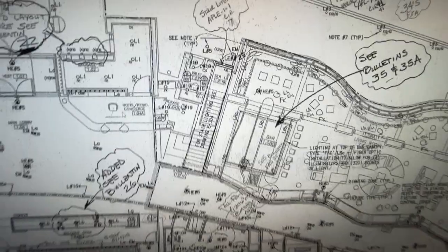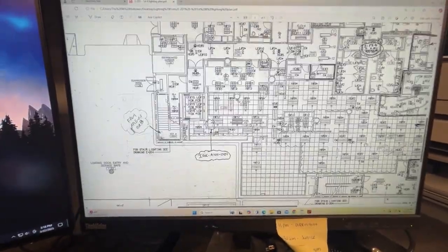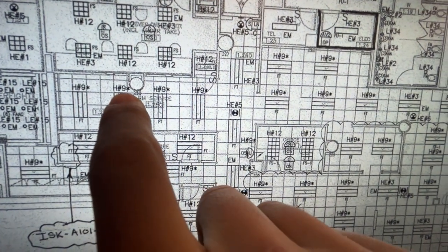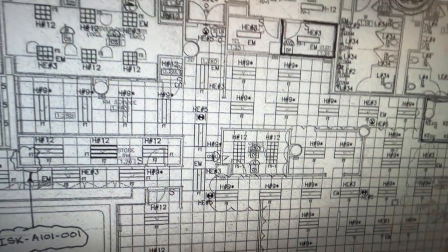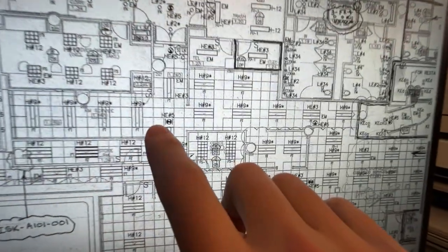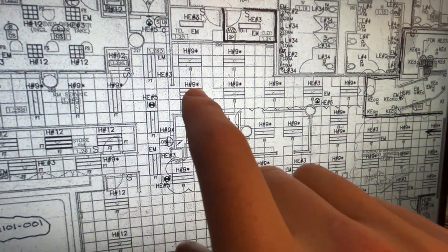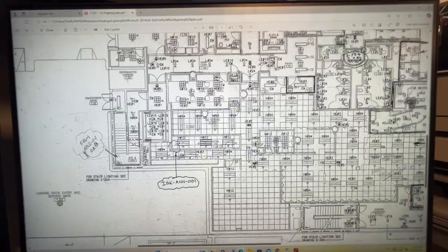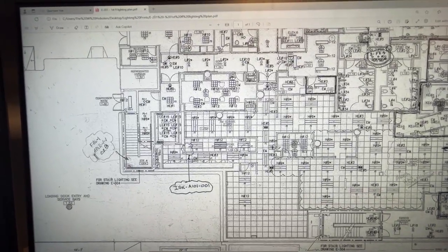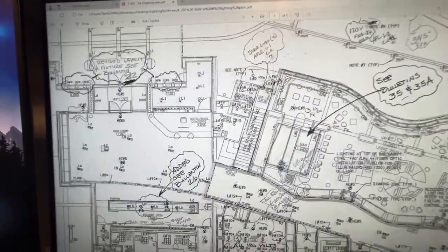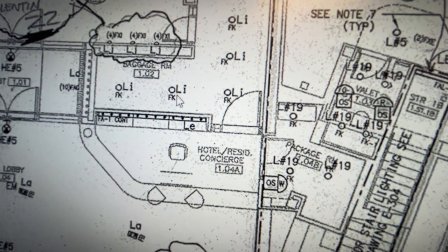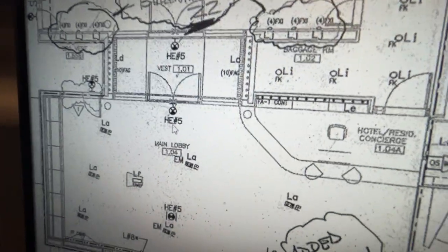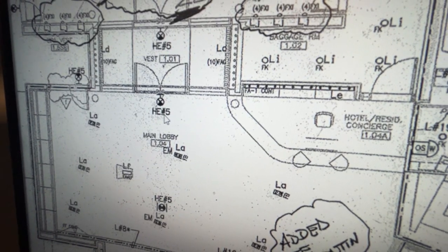So when you're looking at lighting prints, any standard lights in the building are a number for a breaker. So H means high powered, forget about that. It means a high voltage panel. But 9 is the breaker number. However, because Lutron only deals with the dimmer racks, which are much different, they use letters to differentiate. So instead of number 9, it will be letters, LI, LD.